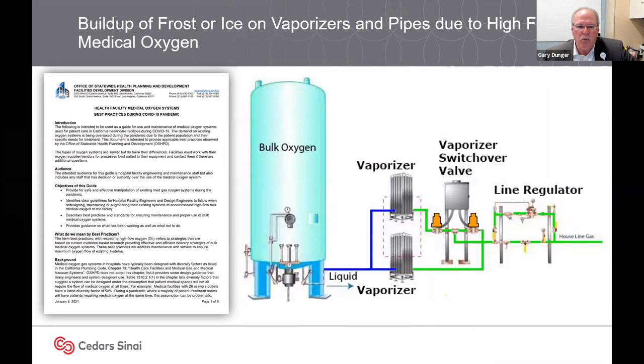One of the things we did at Cedars-Sinai is, as luck would have it, we had multiple vaporizers. With an automated vaporizer switchover valve, we could use one vaporizer for a period of time and then switch over to the other, allowing the previous one to thaw, and keep switching them back and forth so we didn't experience the freezing that some facilities did.